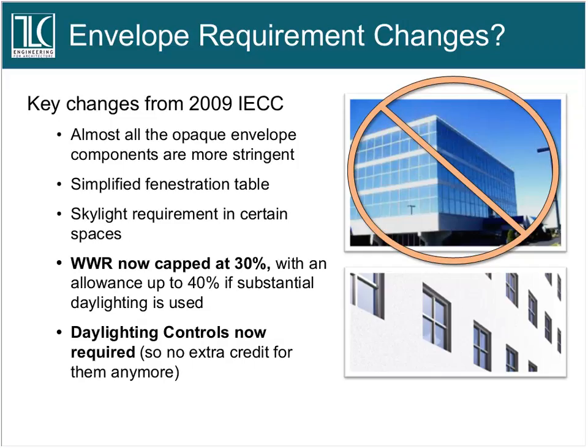And now, because daylighting has been recognized as such an important energy conservation tool, automatic daylight harvesting is now a required part of the code. So we no longer can use daylight harvesting as a way to show better than code. When we were doing LEED projects under version 2009 and before, we often used daylight harvesting to get those better than code numbers that got us LEED points. We can't do that anymore under the new code because daylight controls are now part of the code.